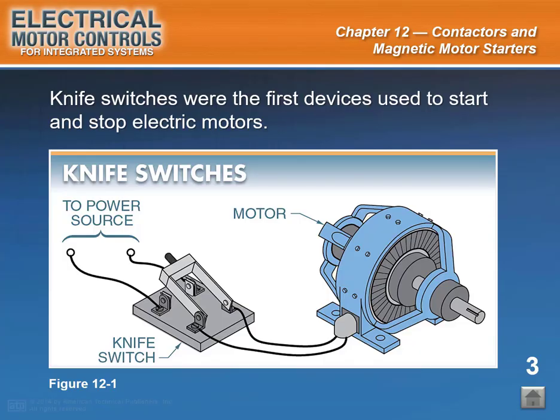In the late 1800s, when electric motors were introduced, a method had to be found to start and stop them. This was accomplished through using knife switches. Knife switches were eventually discontinued as a means of controlling motors for three basic reasons. First, the open knife switch had exposed live parts that presented an extreme electrical hazard. In addition, any applications where dirt or moisture were present made the open switch vulnerable to problems.